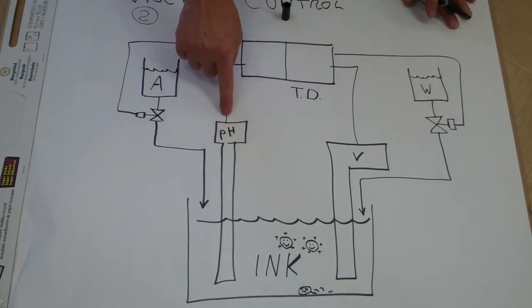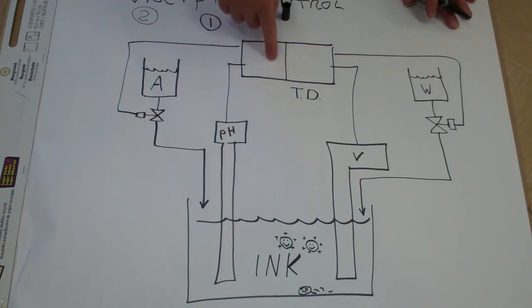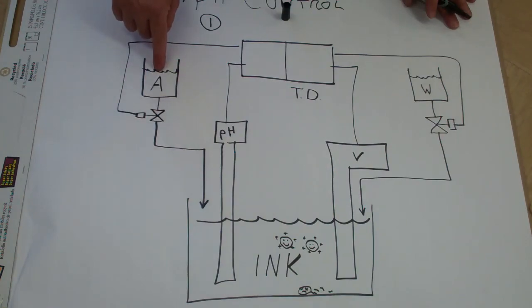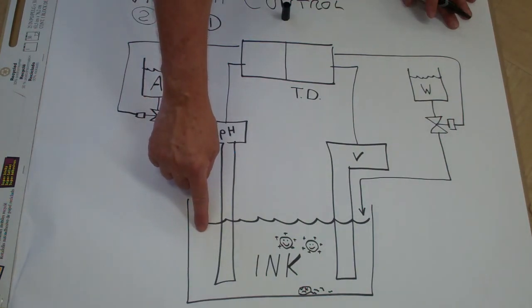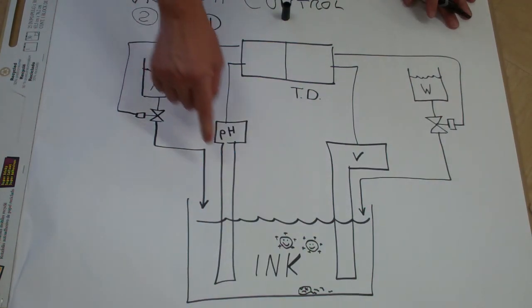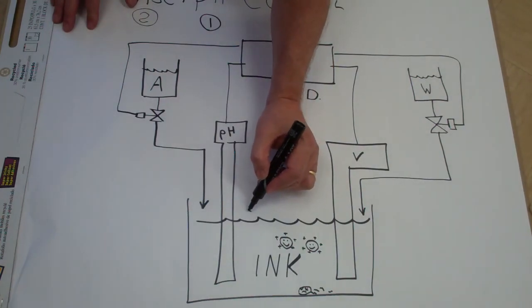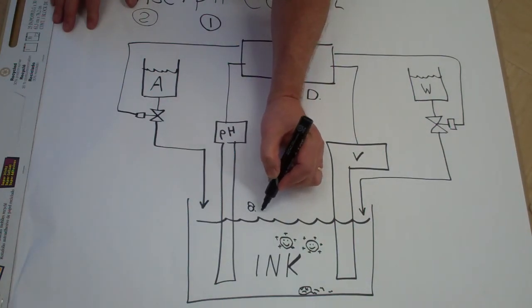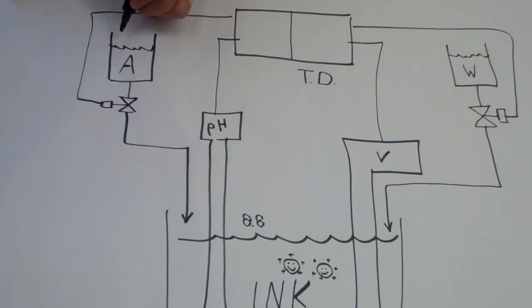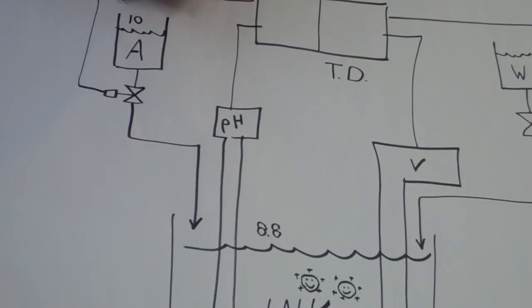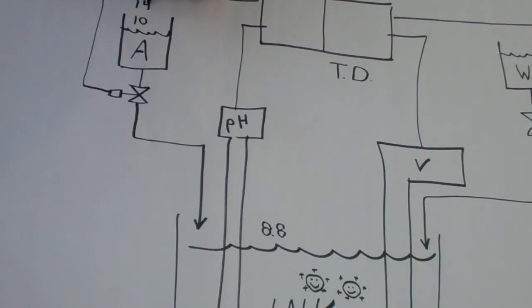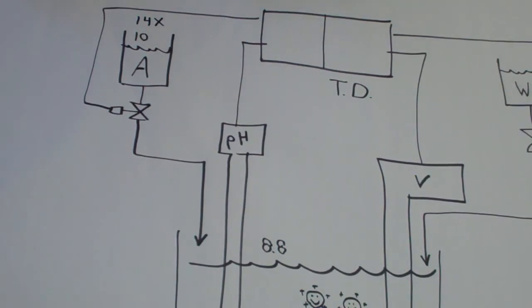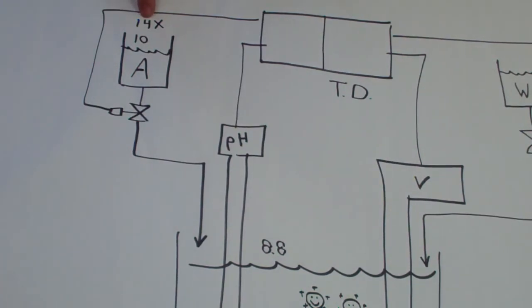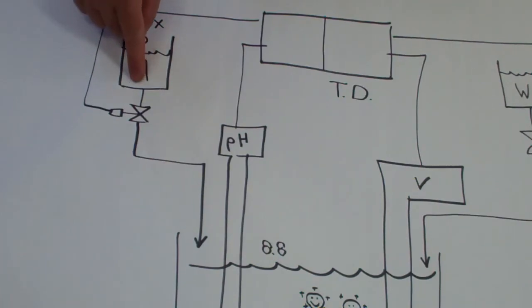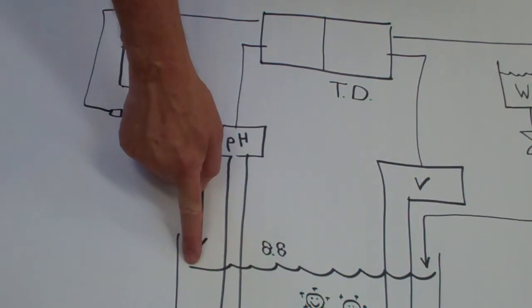So the controller is measuring pH. There'd be a set point here, and the controller sees the pH falling below the desired value. It would open this valve and let some of this amine solution flow into the tank. The amine solution is a higher pH than this. Let's assume you're running 8.8 pH. You'd want this to be maybe a 10 pH. You don't want this at 14 pH. 14 pH is the most caustic level you can get. It'll shock the ink. The solution going down here will be like burning your skin with paint remover.